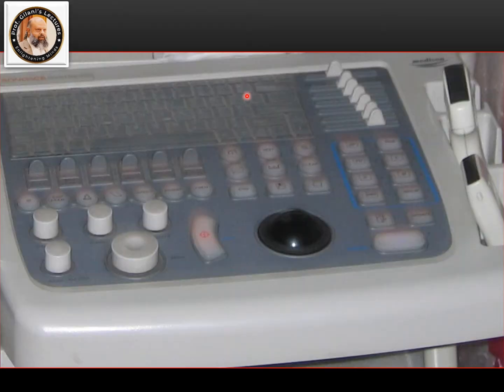Then came the simpler machines with grayscale and color Doppler. And we know that most ultrasound machines have three main components: a pulser, which is a transmitter, which generates pulsed echoes in the form of brief bursts; a transducer, which converts electrical energy to an acoustic pulse, which is the sound energy, and vice versa. So it generates acoustic pulses which travel in the body, and then rebound sounds come in the form of echoes and are recaptured by the transducer.